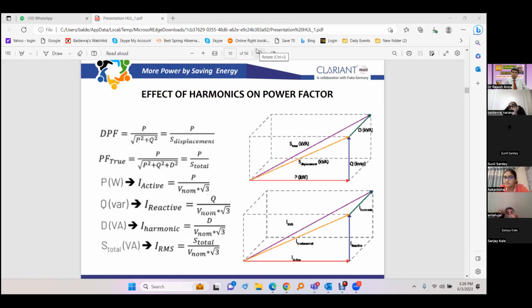So they made some studies and they recommended that to overcome this situation, repeated failures of the RE plants or grid interruptions, we have to have reactive power support by way of STATCOMs, meaning static synchronous compensators, instead of switched capacitors and switched shunt reactors. This was based on some studies they had made, and the industry was not very comfortable with this type of decision, because the plants were ready and waiting to be connected to the grid, and the permissions are not available.